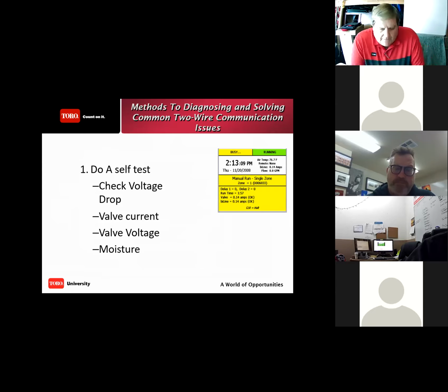First things first. I should have started with this. I apologize I didn't. When troubleshooting, trust the diagnostics of the controller itself. It can be very informative. Turn the clock diagnostics on and ask it to identify how many decoders it reads. What are my error messages? Is it telling me I can only read 50 out of the 65? Is it only reading 12 of the 48? You need to find out.